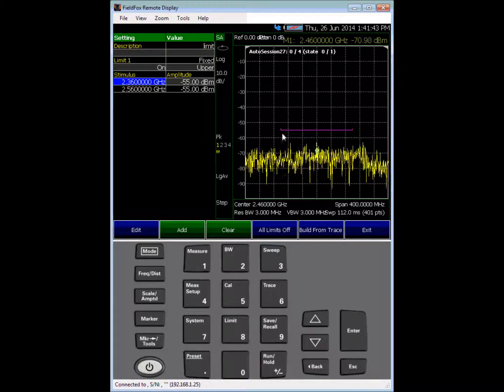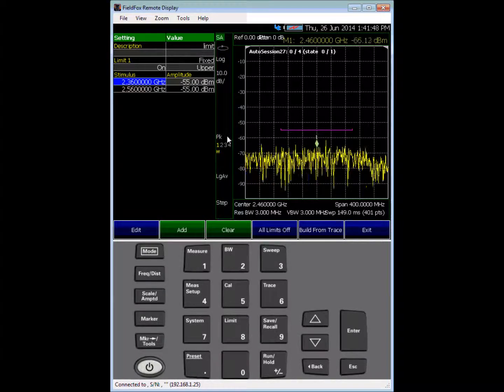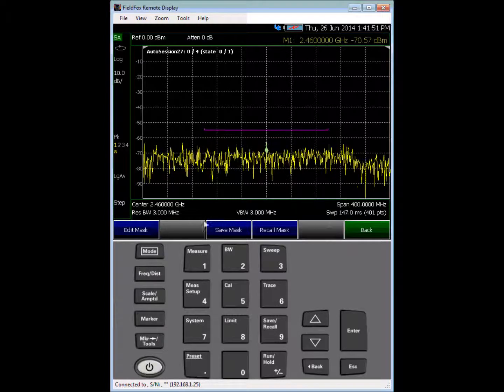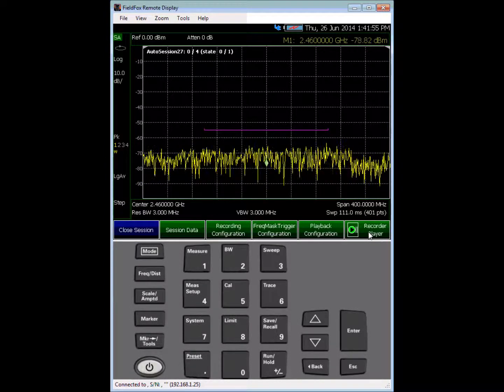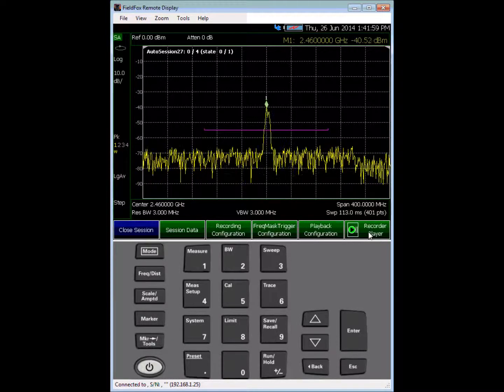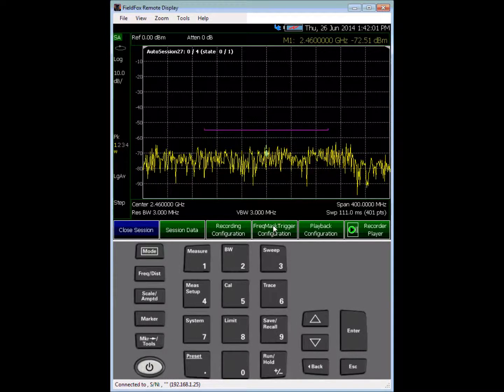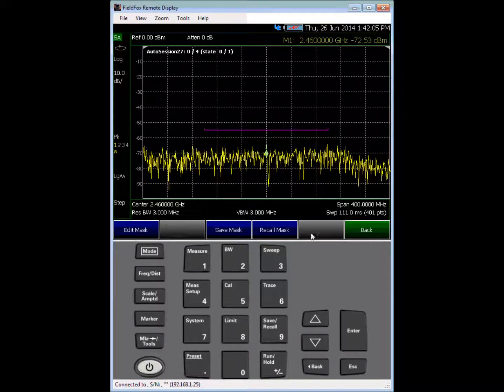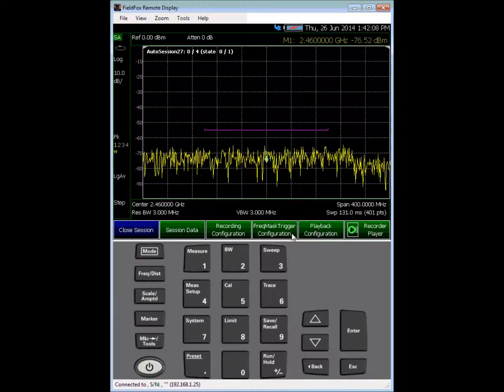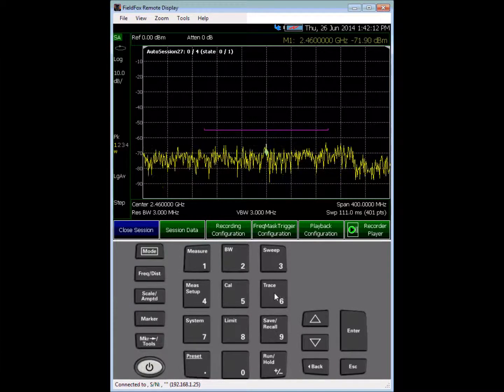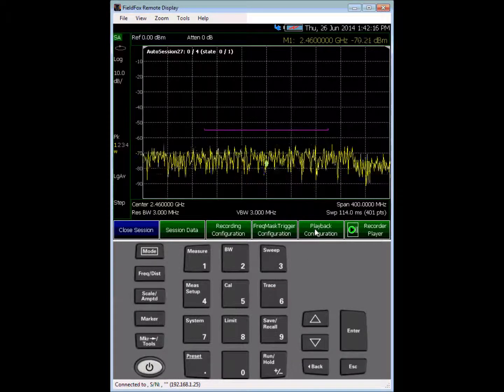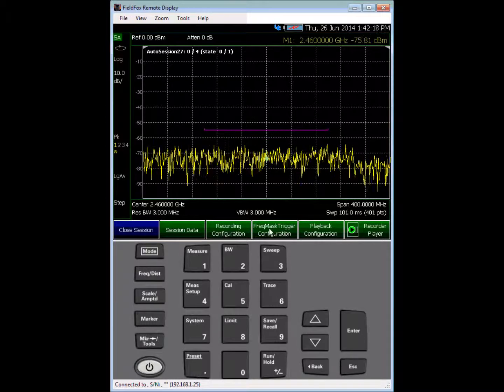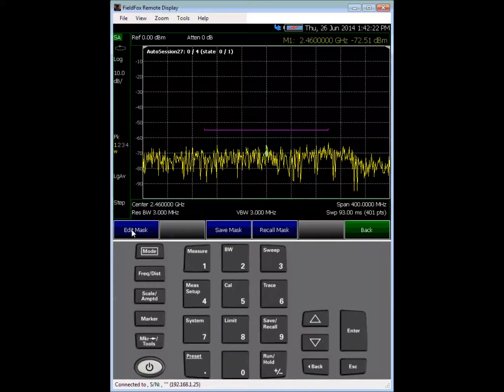So let's exit out of this. What I'm going to do is walk you through the process of creating the mask, saving it and recalling the mask. So if we go to frequency mask configuration, again this is under recording. So we're in spectrum analyzer mode, we go under trace record playback setup, frequency mask trigger configuration.